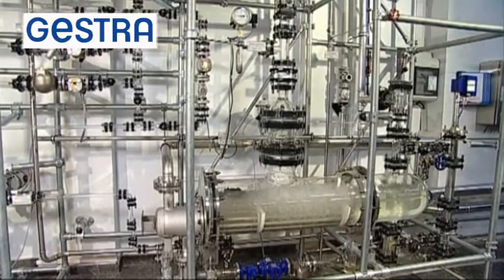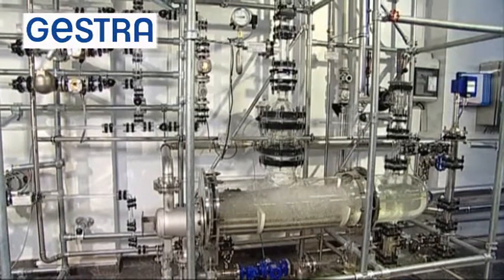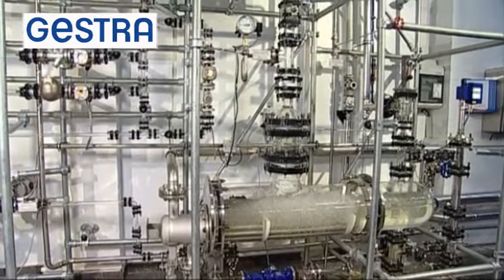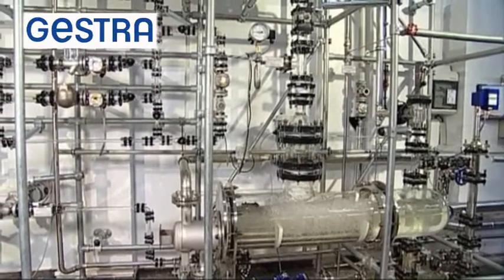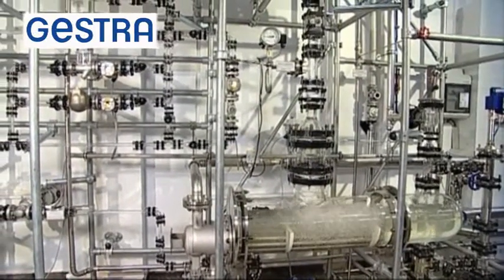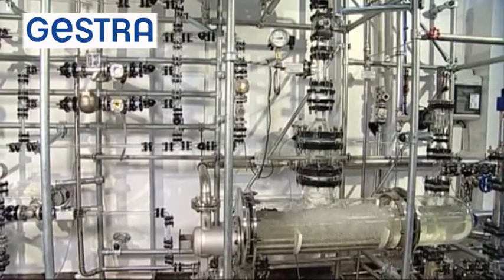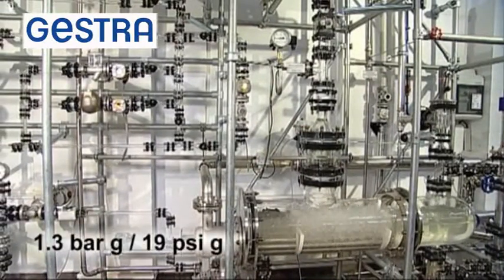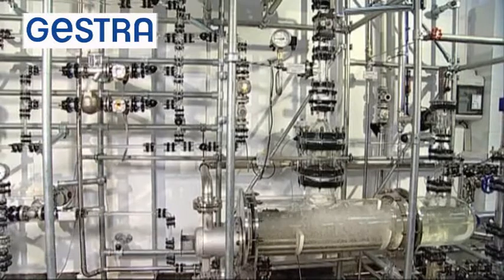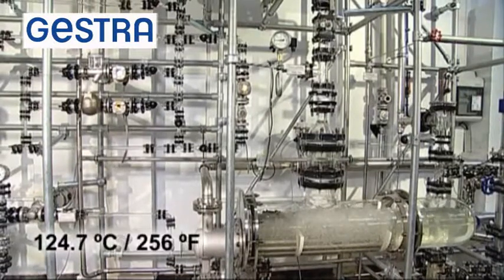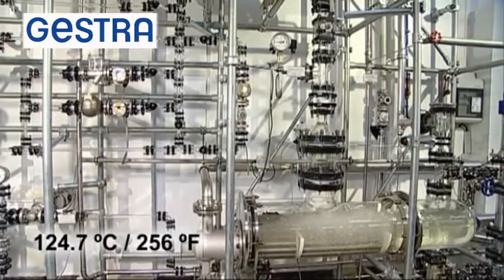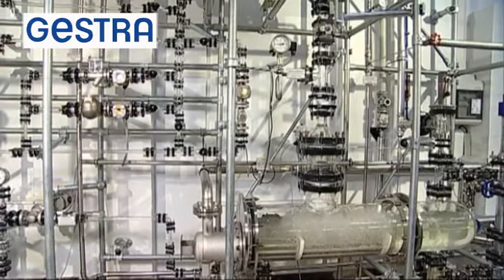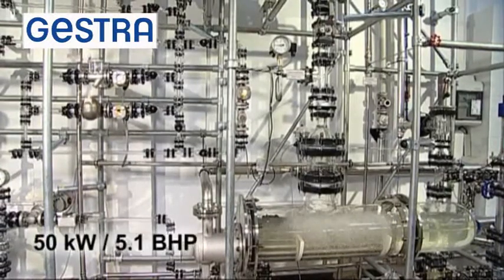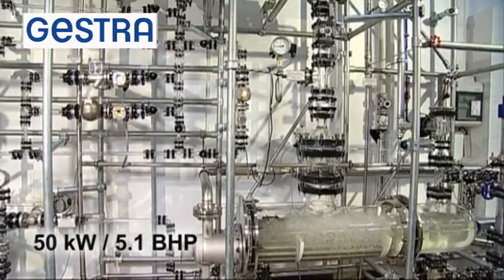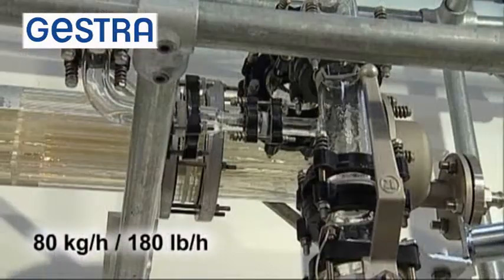This video looks at condensate discharge using various kinds of steam traps, as demonstrated in the glass steam system of GESTRA AG, Bremen. The steam system consists of a secondary steam generator with a surface pressure of 1.3 bar G, corresponding to a saturation temperature of 124.7 degrees centigrade. The capacity of the steam boiler is 50 kilowatts, which yields a steam flow rate of 80 kilograms per hour.